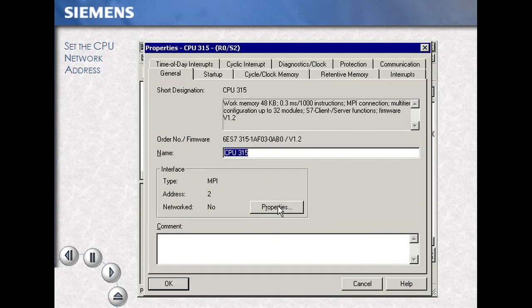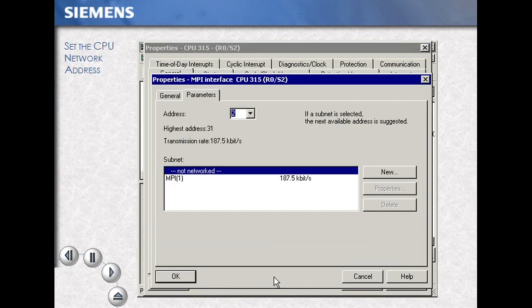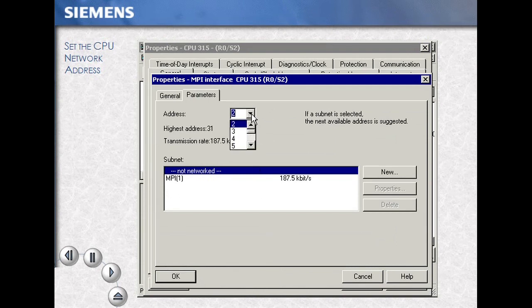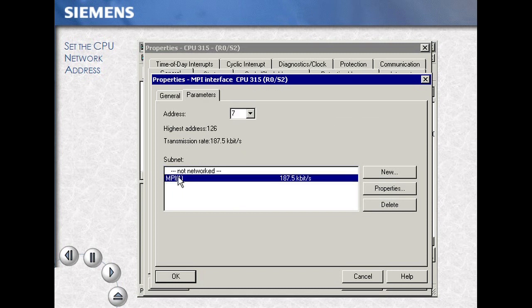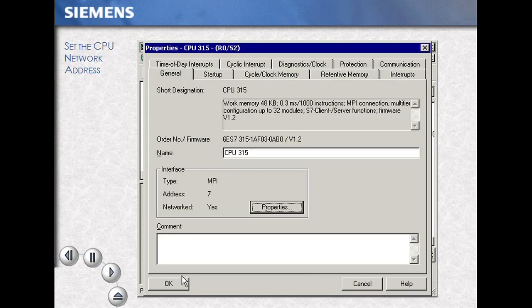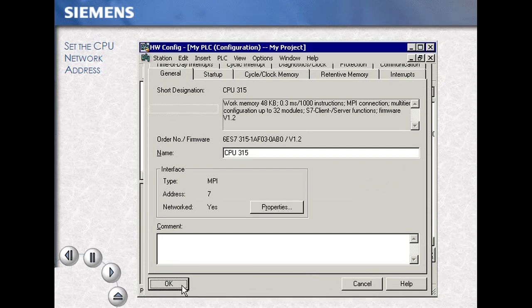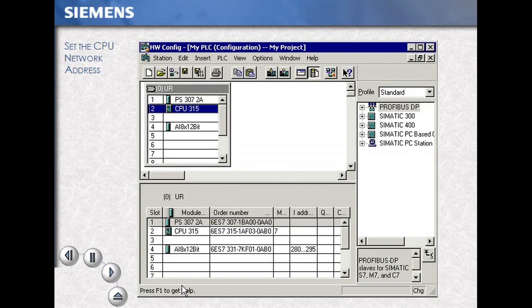Select the Properties button and change the address, assigning your address to this CPU. Select MPI to link it to its associated network, then OK. OK confirms your setting, then save and compile your work.